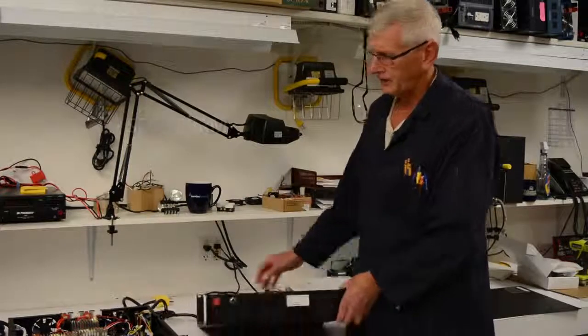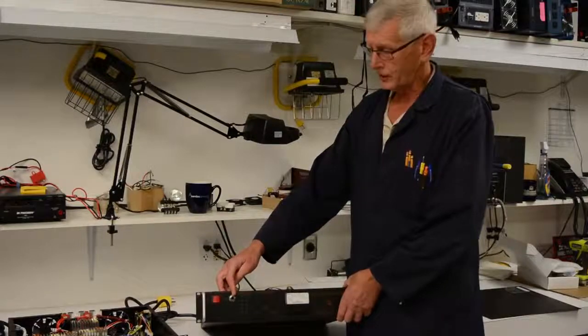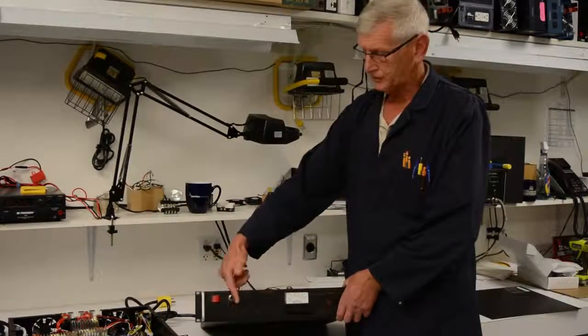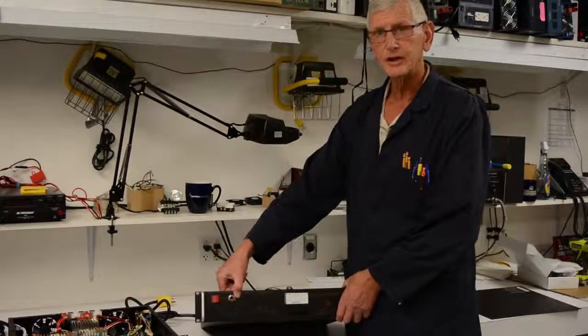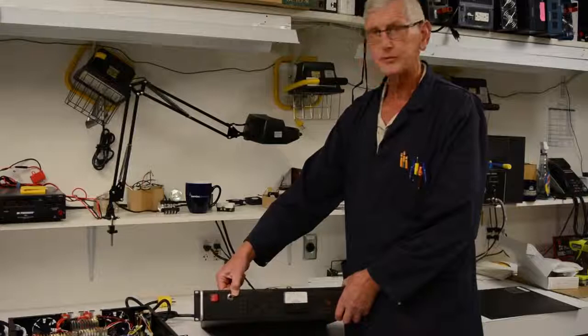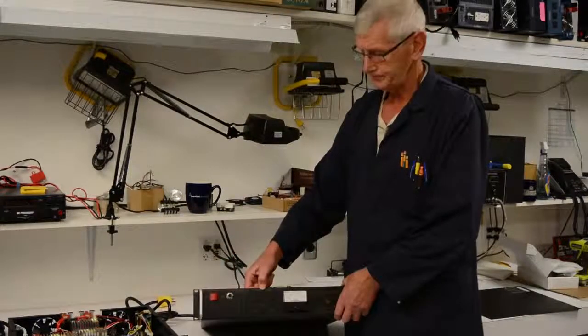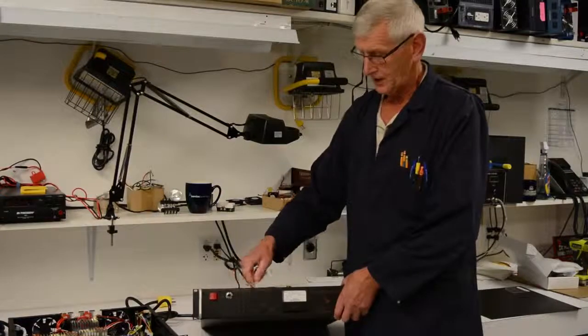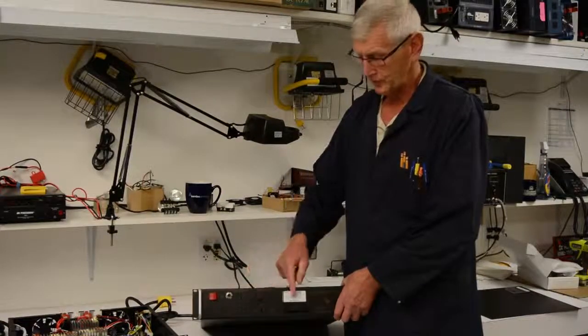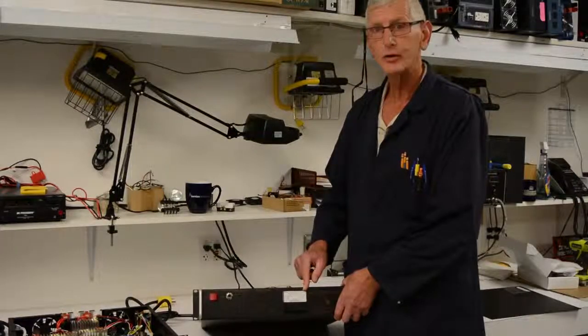On the front face plate, we have the on-off switch, a breaker for overloads, the status of the power supply modules. This one has two LEDs because it has two modules, each at 20 amps or 40 amps total. A fan failure alarm LED indicator. A volt and amp switch for the meter on the front here, which will show you the status of the power going out of this unit.